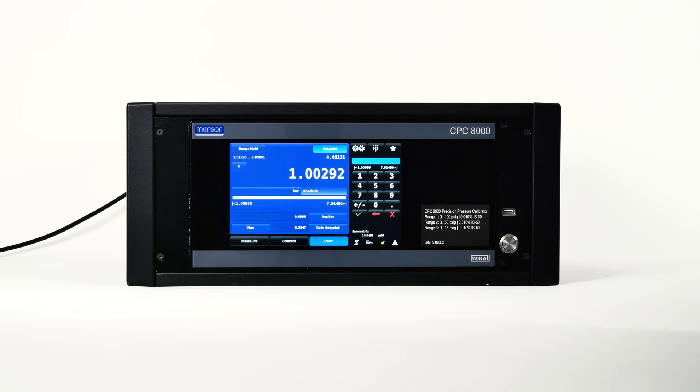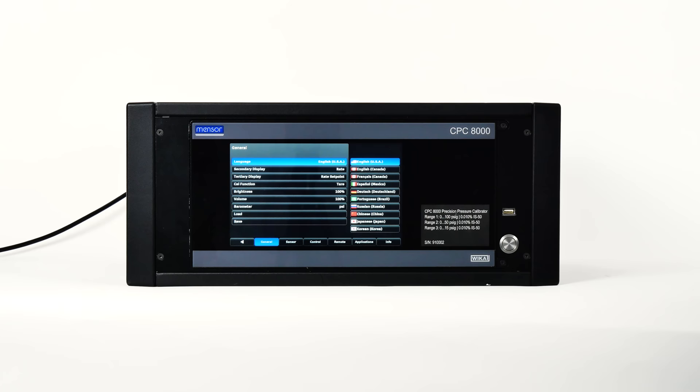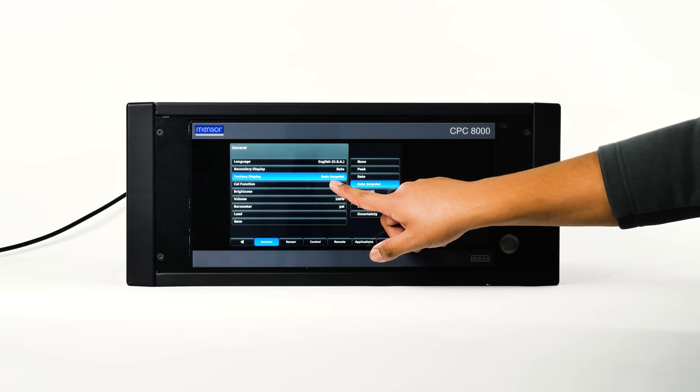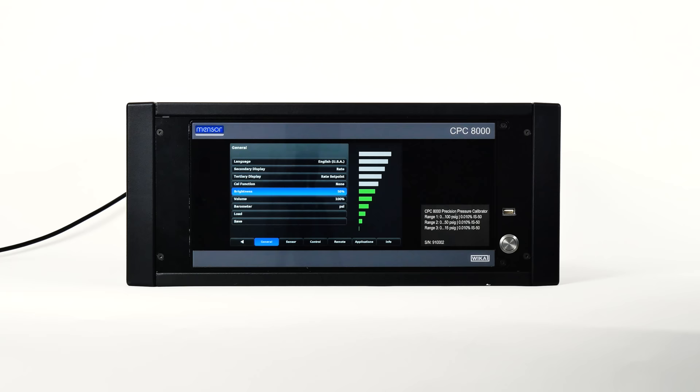You can configure the CPC-8000 using the setup button. Let's navigate to the general tab, where you'll find language options. The secondary and tertiary display areas provide a place to indicate extra data during test or calibration — clicking either will show the choices available. The cal function button provides a selection to enable the zero button on the main screen; selecting zero enables it, none disables it, and the tare option enables the tare button. The brightness setting provides a sliding scale to increment the screen brightness across all screens.